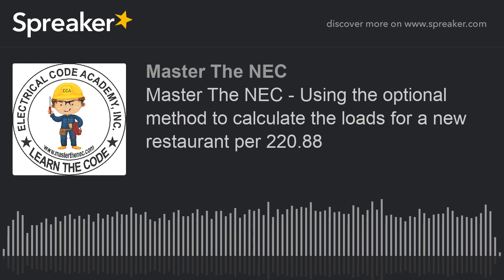So it's 450 kVA, so we're in the third one down from the left side, and that's 326 to 800. Now let's go to the right. And here's where people get confused. They will take that 450, and they will do it at 50%, and then add the 172.5. And that is not the way to do it. Probably 8 out of 10 people do it that way because they don't understand the concept of working the parentheses first and then solving your problem.